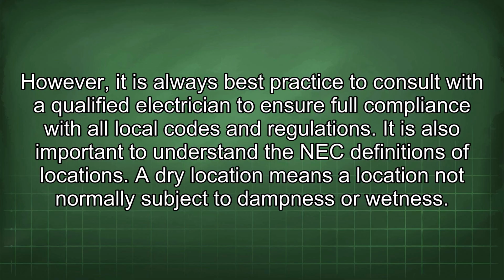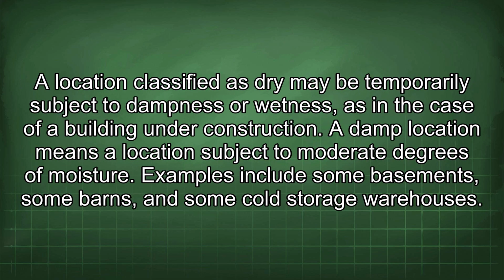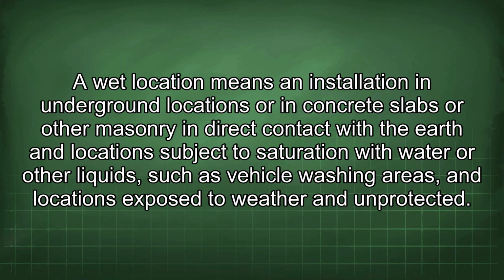A dry location means a location not normally subject to dampness or wetness. A location classified as dry may be temporarily subject to dampness or wetness, as in the case of a building under construction. A damp location means a location subject to moderate degrees of moisture. Examples include some basements, some barns, and some cold storage warehouses. A wet location means an installation in underground locations or in concrete slabs or other masonry in direct contact with the earth, and locations subject to saturation with water or other liquids such as vehicle washing areas, and locations exposed to weather and unprotected.